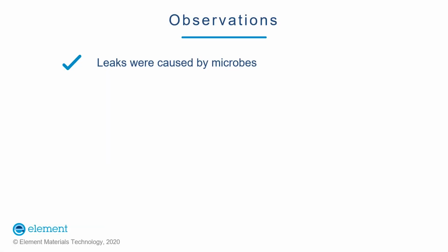Based on the shape of the pits, the unusual selective phase attack, oxide deposit color, its distribution pattern, and EDS results, it was proven that the corrosion and subsequent leakages in the stainless steel pipe is caused by microbiologically influenced corrosion, also known as MIC. This failure mechanism is caused by microbes that attack the steel material, in this case, selectively attacking the ferrite in the welds.